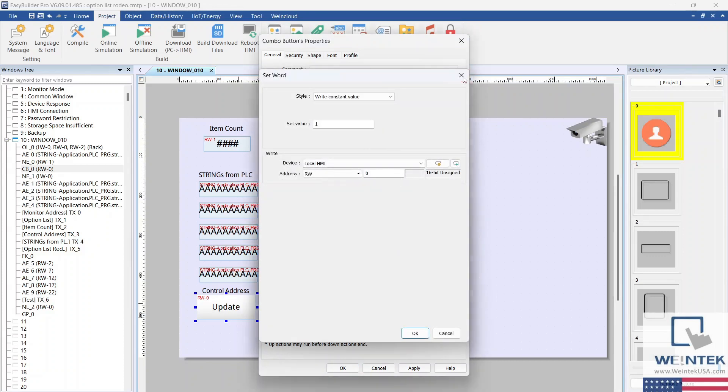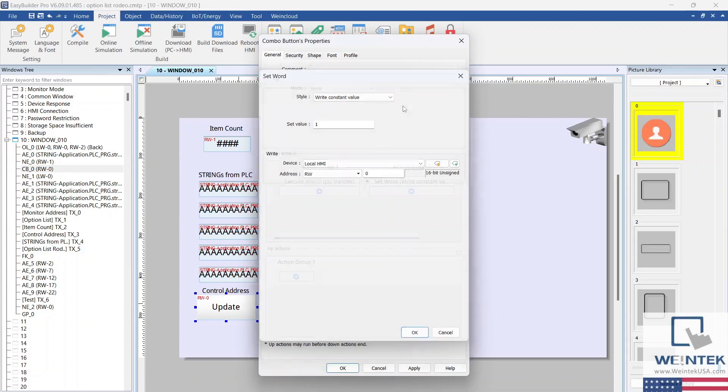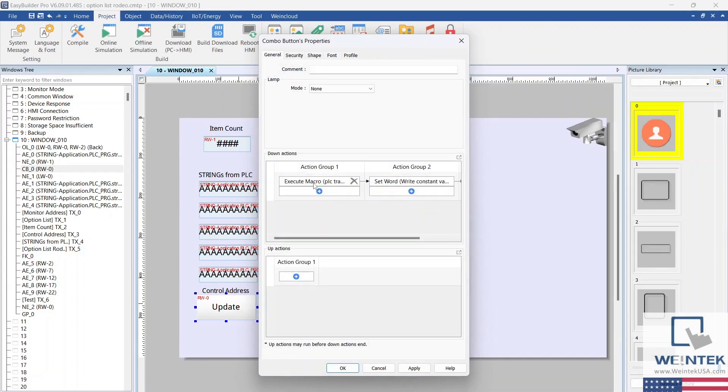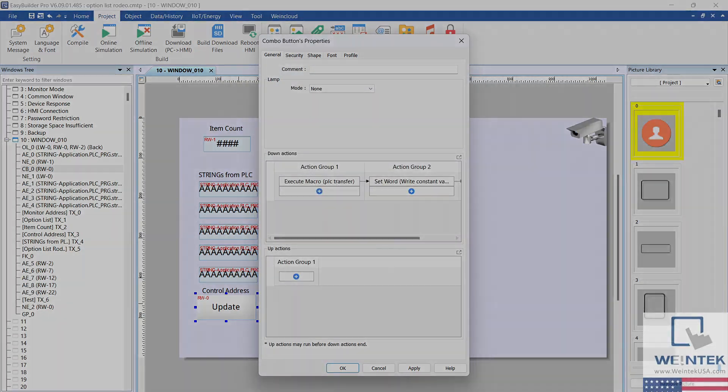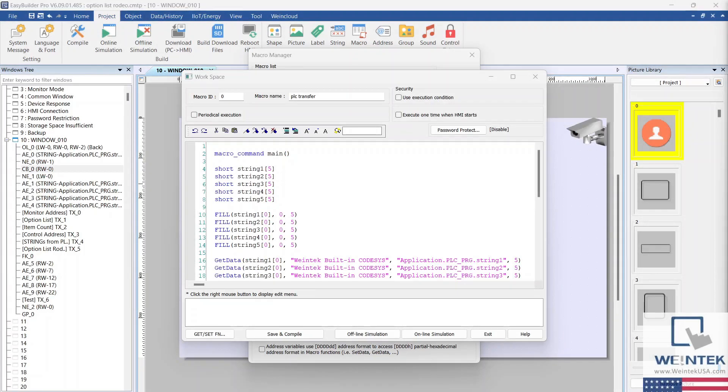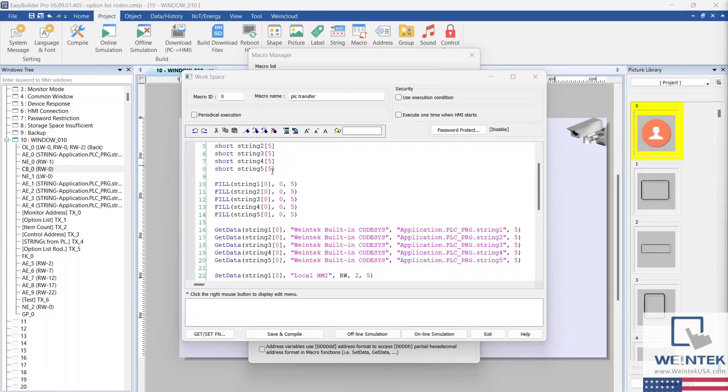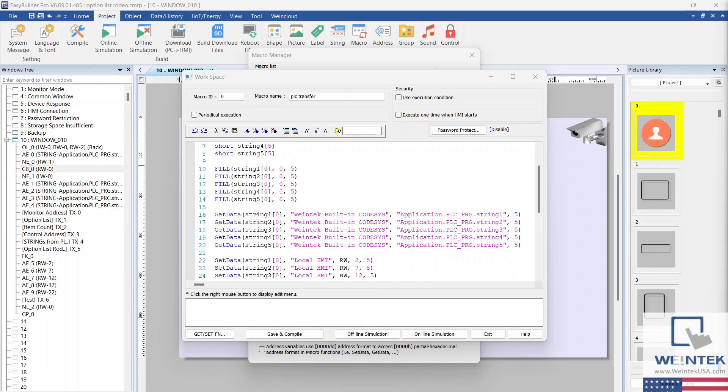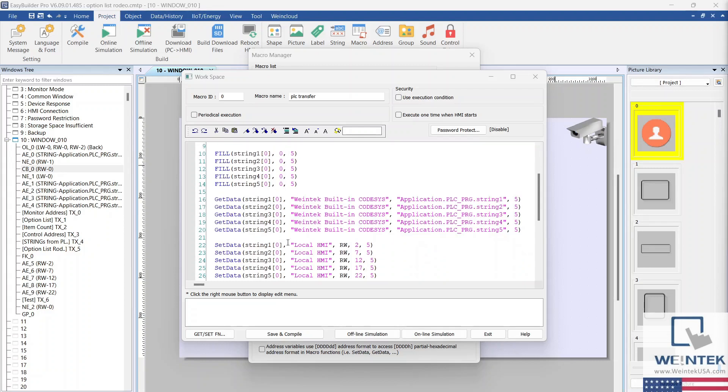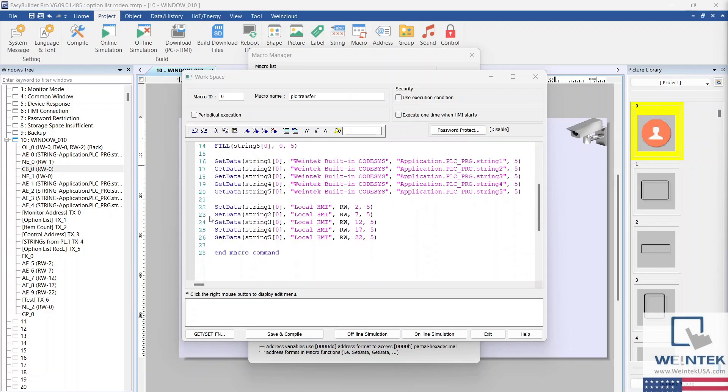The macro gets data from the registers addressed to the PLC, in this case, our CODESYS project, and sets the string data into the registers addressed to the option list. Selecting the Execute One Time When HMI First Starts option will update the contents of the option list upon HMI reboot.